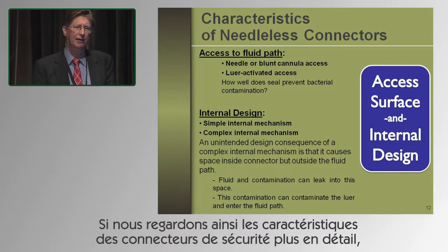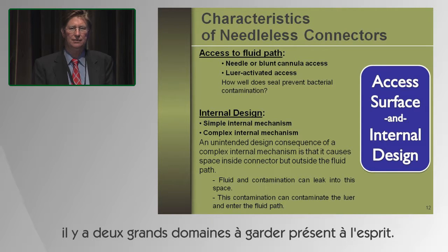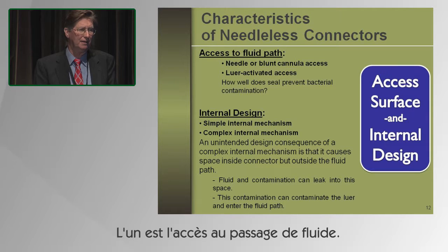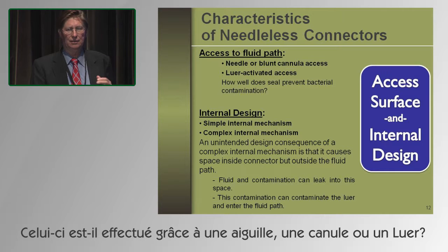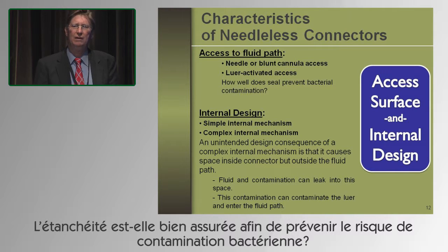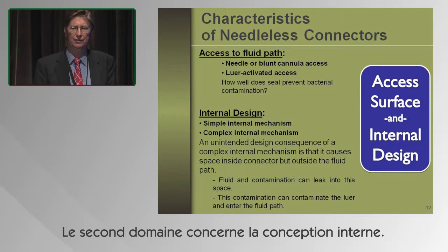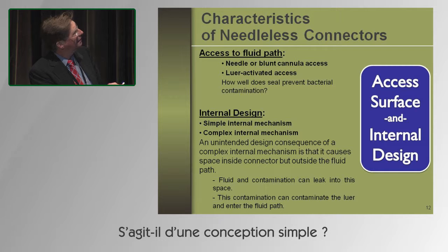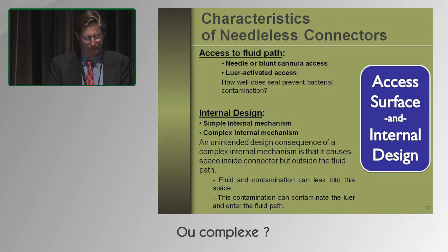So if we look at characteristics of needleless connectors, there are 2 major areas to keep in mind. One is access to the fluid path. Is it done through a needle or a blunt cannula, or is it through luer-activated access? And how well does it seal to prevent bacterial contamination? Second is the internal design. Is it a simple design, or is it complex?